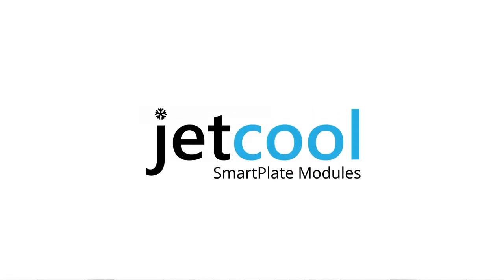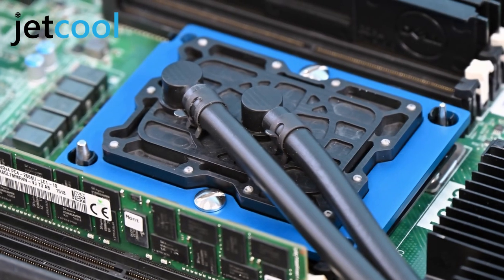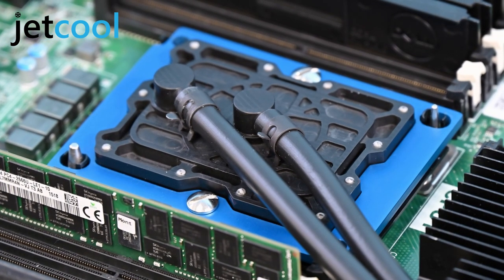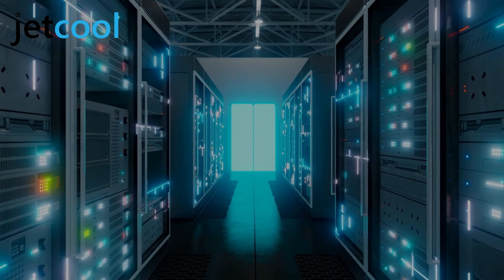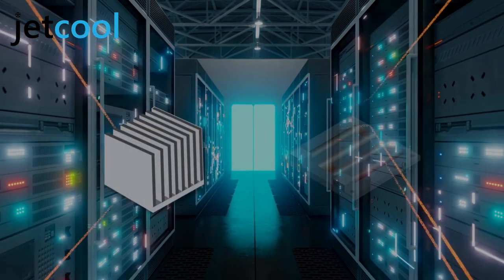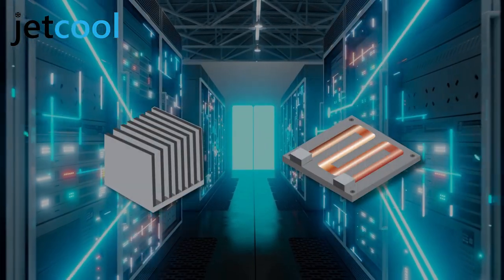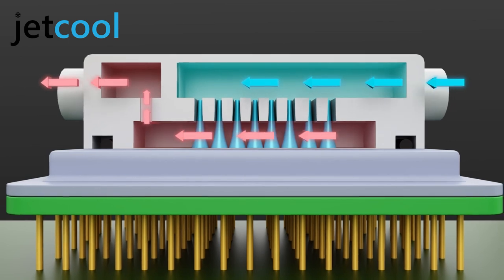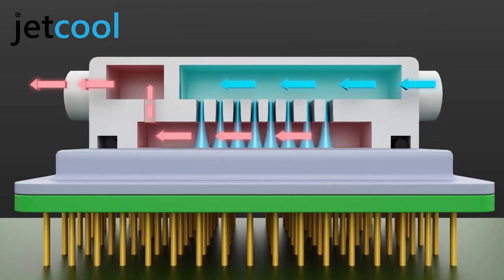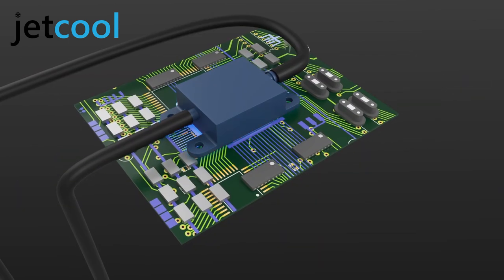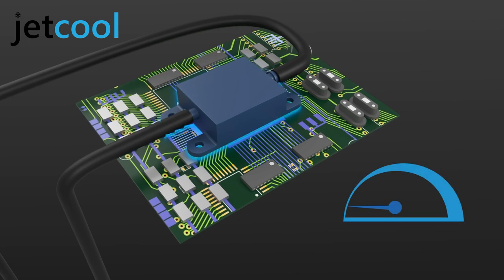JetCool has integrated its microconvective cooling technology into a novel, fully sealed cold plate design. Unlike typical heat sinks or cold plates that pass fluid over a surface, SmartPlate modules utilize an array of jets that route fluid directly at device hotspots, enabling customers to cool devices beyond 1500 watts TDP.